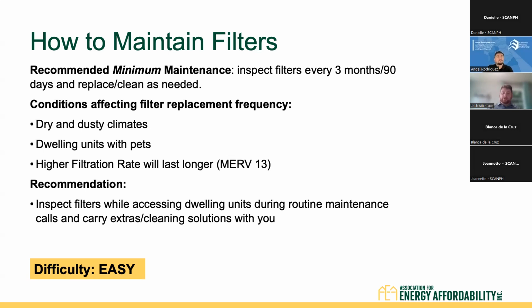And as a property manager, property owner, or maintenance staff, replacing a filter in every single unit every 3 months is going to be a difficult task. Really, accessing the unit is probably the most difficult thing. So you should have your maintenance staff carry filters and cleaning solutions whenever they access a unit for routine maintenance. They should be inspecting the filter while they're in there. And then you should put together some sort of tracking solution to make sure you're not missing units that need a filter replacement. You'll see this throughout the presentation, but on the bottom left, I have a difficulty rating. This is intended for folks to understand whether this is something that can be handled in-house, or something I should hire a vendor for or budget for a vendor, etc. So starting off with filter replacements, the difficulty is considered easy.